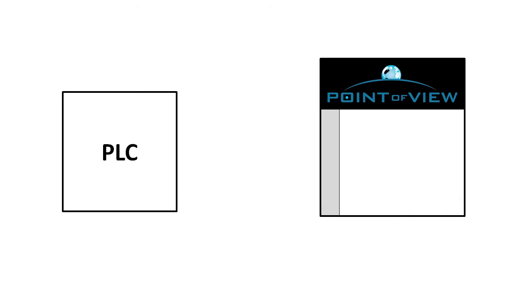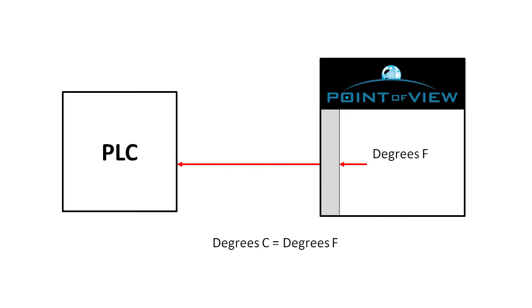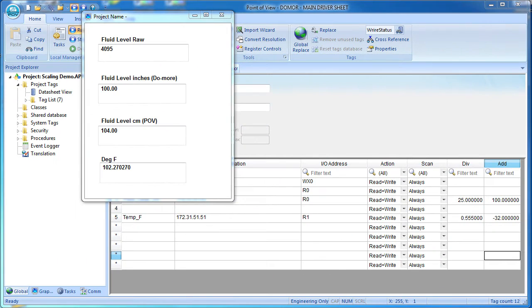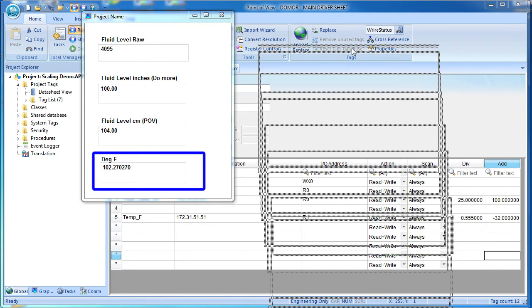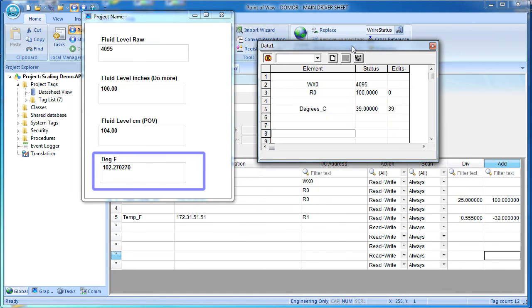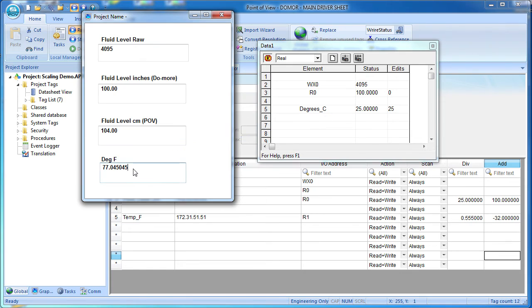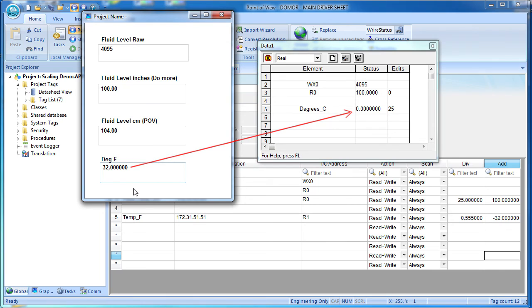That is, if Point of View writes data back out to the PLC, it does the exact opposite. It takes its degrees F, subtracts the minus 32 and multiplies it by 0.55. So the PLC always sees degrees C and is never aware that this scaling is being done in Point of View. Let's run this example. Here is the Point of View screen. I added this degrees F text box and a Do-more data view. If we enter 25 degrees C on the Do-more, then Point of View sees 77 degrees F. If we enter a 32 degrees F in Point of View, then the PLC sees 0 degrees C. Exactly what we expect.